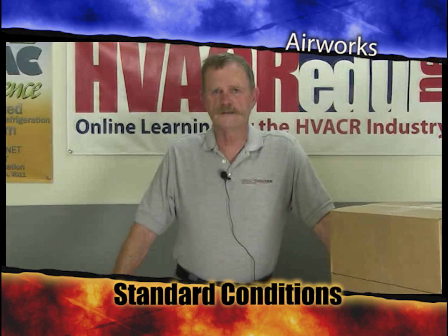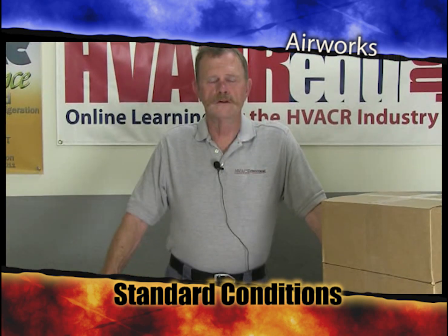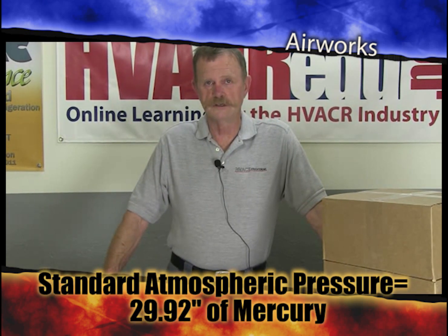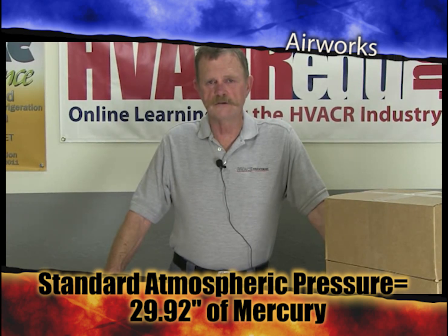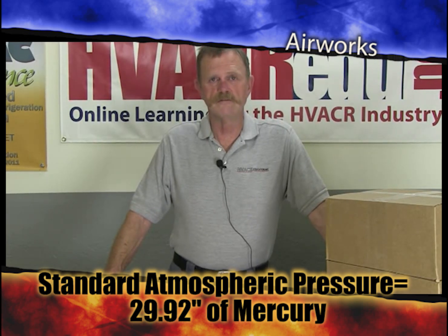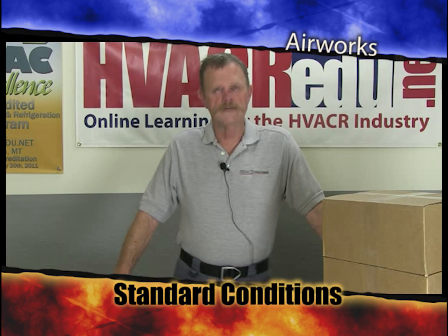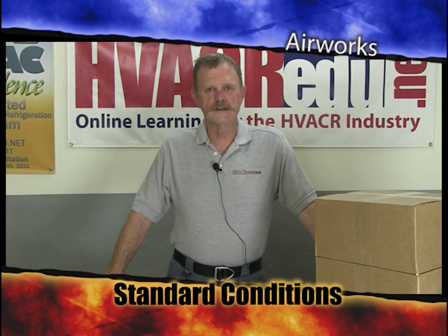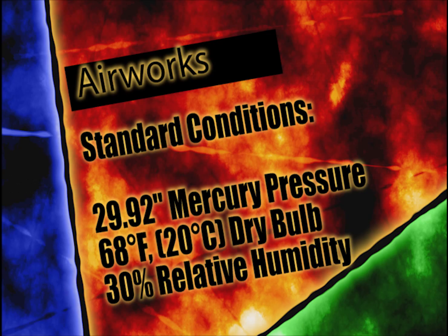Standard conditions exist under very specific conditions. One of the conditions is that you're at atmospheric pressure, or standard atmospheric pressure, which is 29.92 inches of mercury pressure. That is a standard atmospheric pressure, found normally at sea level, but it can vary from where it's found. The other condition that exists is at 68 degrees Fahrenheit. That would be the dry bulb temperature that you would have to have standard conditions. The other condition that exists is 30% relative humidity. So you have a number of things that determine standard conditions. 29.92 inches of mercury, atmospheric pressure, 68 degrees Fahrenheit dry bulb, and 30% relative humidity.